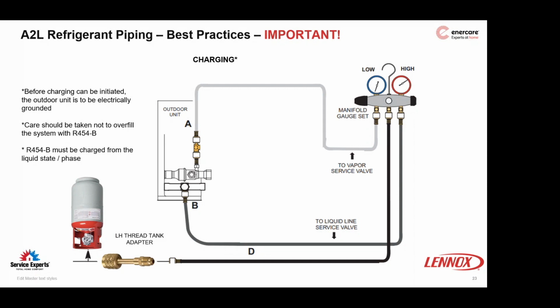We did mention, yeah, if God forbid you have to use the line set, you're stuck. The homeowner's not going to let it happen. The line set is appropriately sized and you can still use it. Yes, definitely flush it. The oils are not the same. They are very similar, but not exactly the same. The manufacturers all still suggest flushing the piping system if it has to be used, regardless of what refrigerant was there before. Okay. Thank you. Yep, no problem.